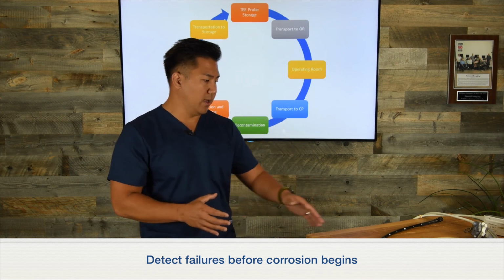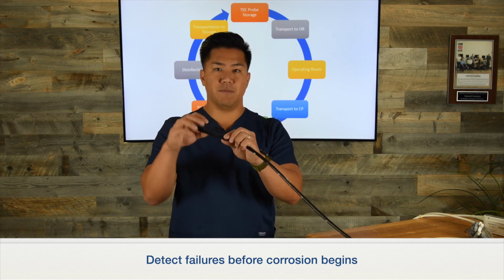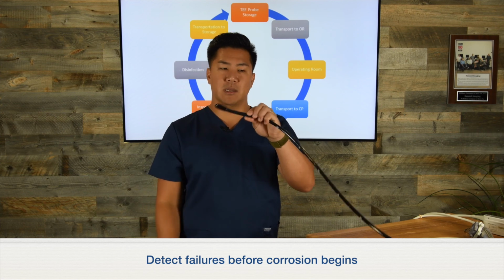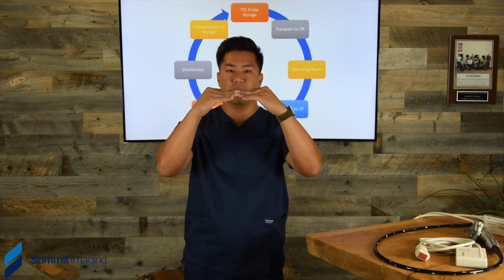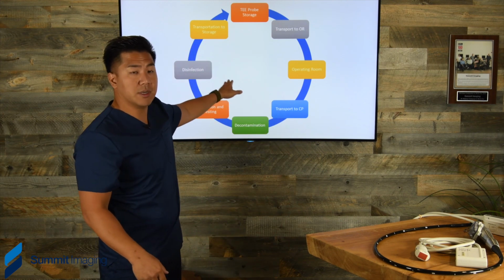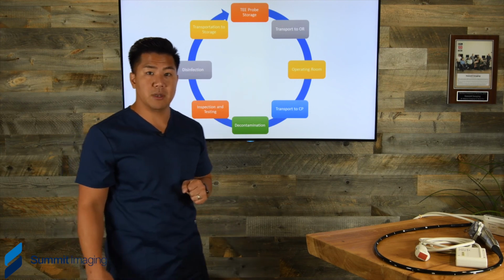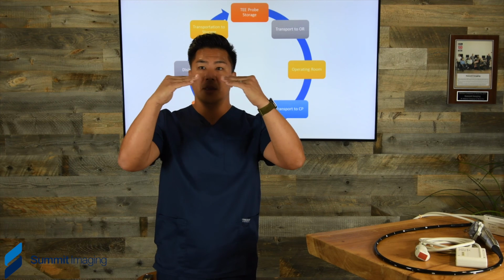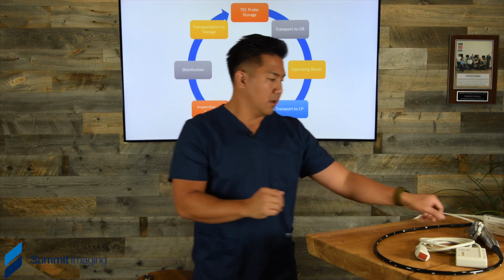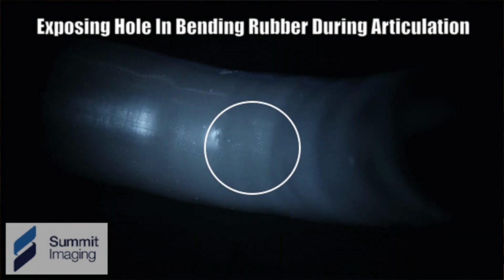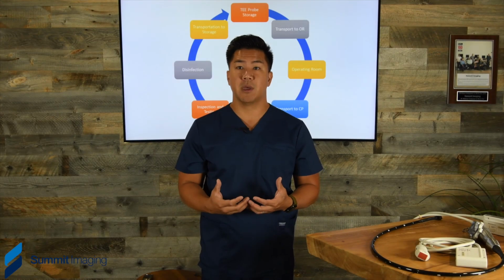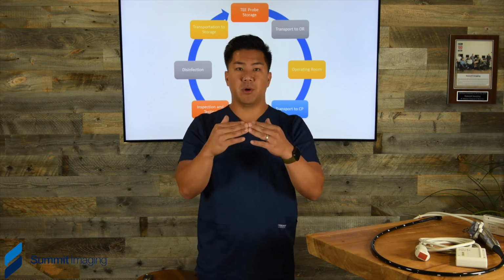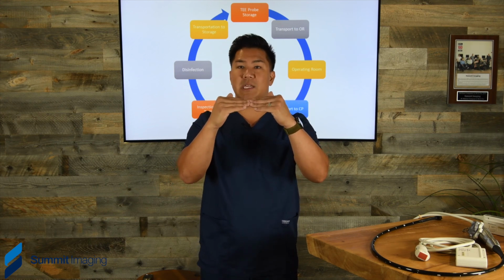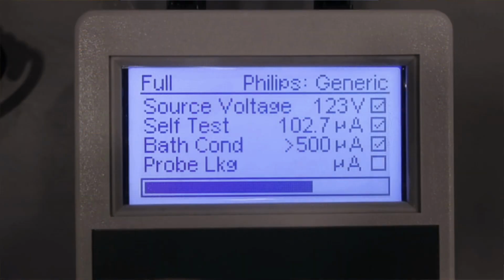And so the important part here is that because this is a bending rubber, if there is a puncture and it's straight and it's relaxed, the rubber naturally comes back together. And if it gets into disinfection and then during disinfection you do a leakage test, that puncture is now relaxed and pushed back together. But when it's articulated like this, it now exposes that puncture a little bit, and then that would happen during a scan or some other part of the process where the rubber, by virtue of the material, when it's relaxed, it can actually cover things up and actually pass a leakage, but the moment you bend it, it will actually open that up and it would fail leakage at that point.